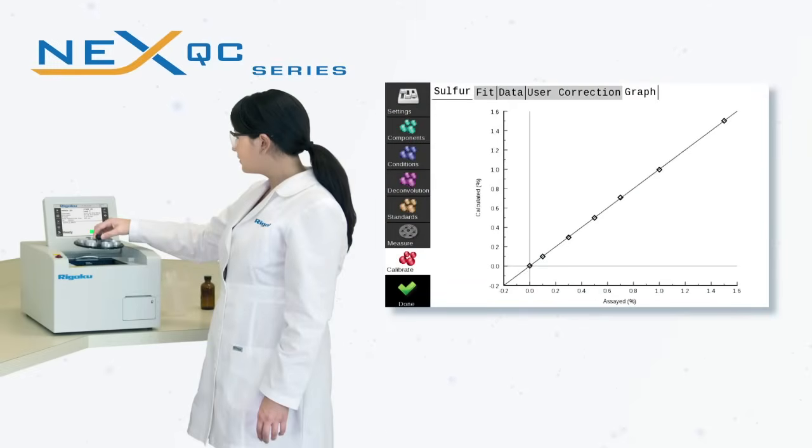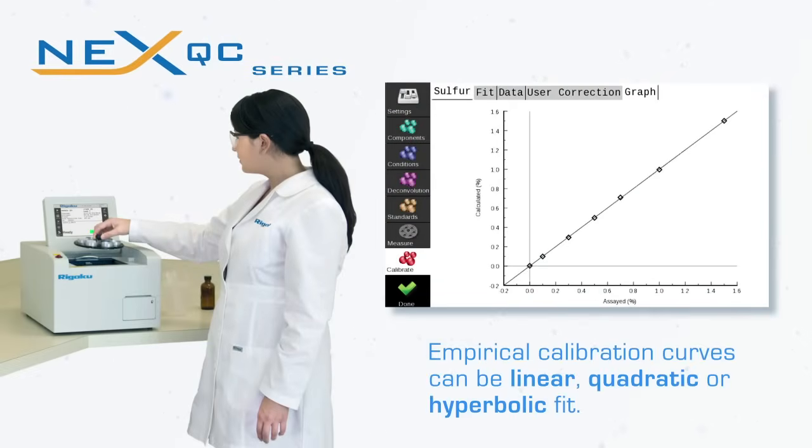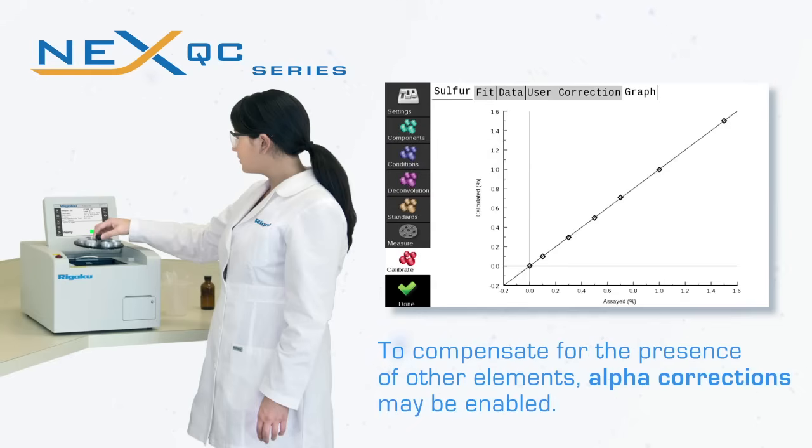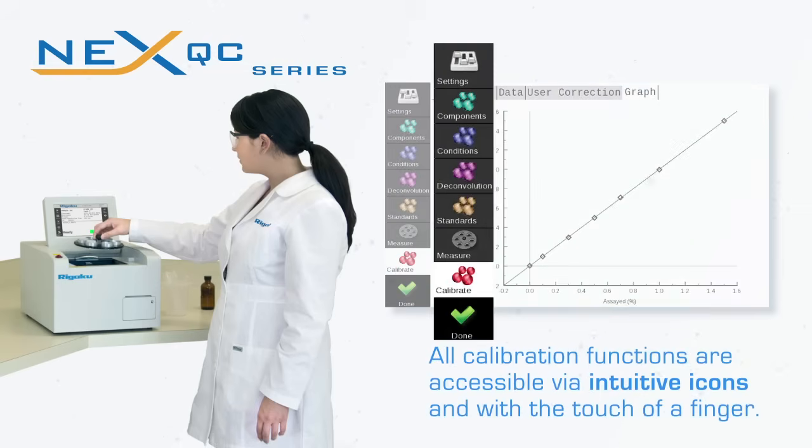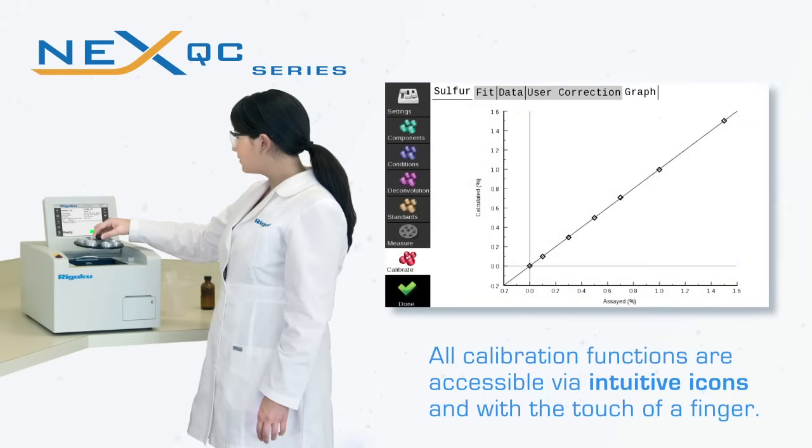With the NEX QC series, empirical calibration curves can be linear, quadratic, or hyperbolic fit. In addition, to compensate for the presence of other elements, alpha corrections may be enabled and are automatically calculated given sufficient standards. All calibration functions are accessible via intuitive icons and with the touch of a finger.